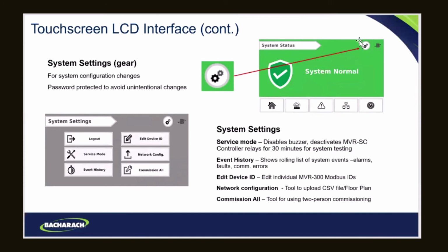The settings gear on the home screen, and actually I think you get this on most of the screens that you have. This will take you into the settings screen, and you get into some kind of inner workings of the controller itself. There's a service mode where it'll disable all the buzzers and stuff for 30 minutes for testing. That way you're not scaring people out of their rooms when you're sitting there testing your system.